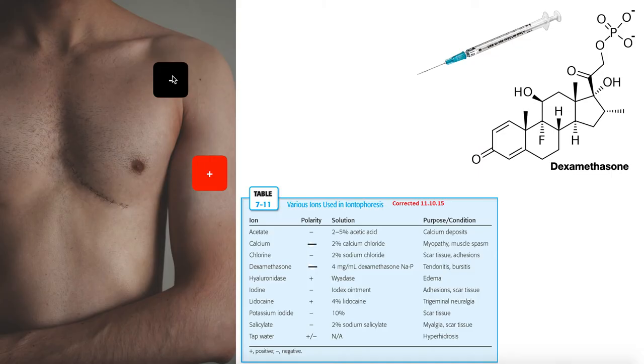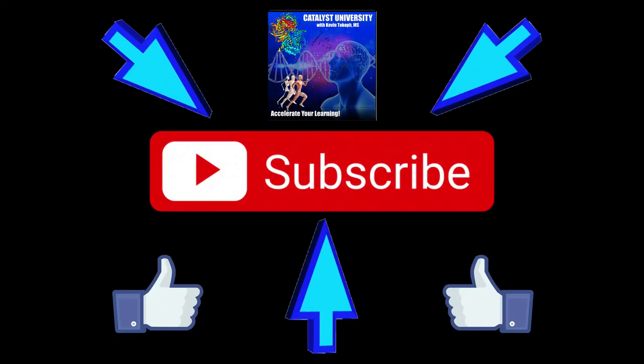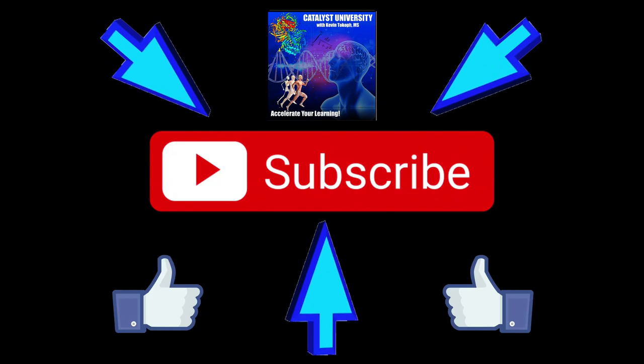So once electrodes are placed, wires plugged into the machine, and the machine is programmed — for example, 3 mA for 20 minutes — that delivers a dosage of 60 milliamp-minutes, right in the middle of the target range. Hopefully this gave you a good overview of iontophoresis and how it's performed. Please like this video and subscribe for future videos. Thank you.